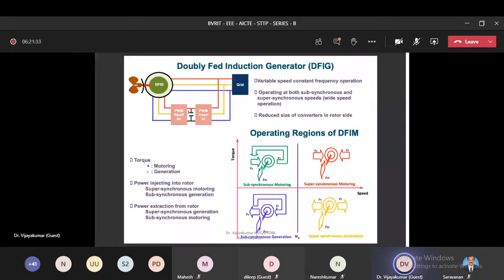With battery storage, we can charge and discharge the battery—discharging it to supply power to the converter as input. That's what we've done. The advantage of removing the converter at the grid side is that you eliminate harmonics injection into the grid, because any converter or power electronic switch connected to the supply will pollute the system. So we simply removed that grid-side converter and connected the battery instead.